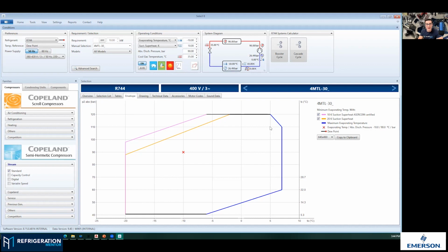Everything was running fine. And come to find out, it was a ZO compressor, and the maximum continuous current was like 5.5, I think, amps. And in the drive, it was set for 16 amps. So the maximum that the drive could run was 16. So what was happening, it was overloading the compressor consistently for a couple months until the windings failed.